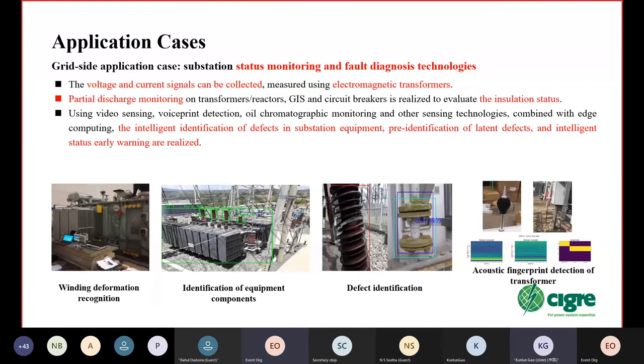In the substation, status monitoring and fault diagnosis technology are used. Voltage and current signals can be collected by sensors and measured using electromagnetic transformers. Partial discharge monitoring on transformer reactors, GIS, and circuit breakers are realized to evaluate insulation status.